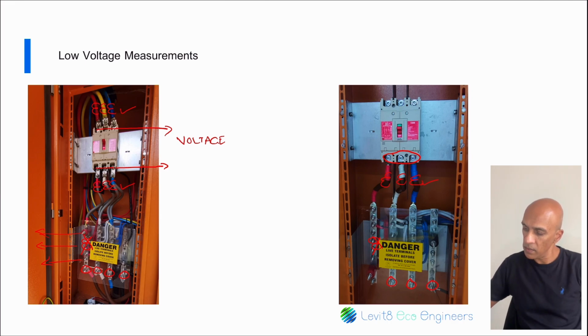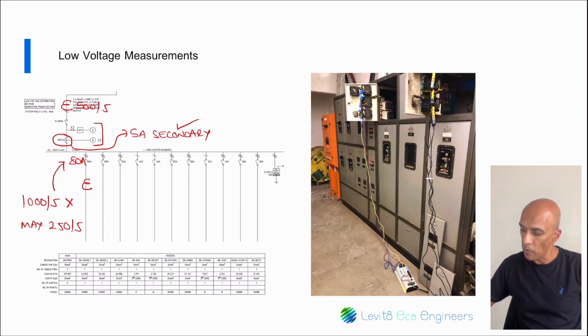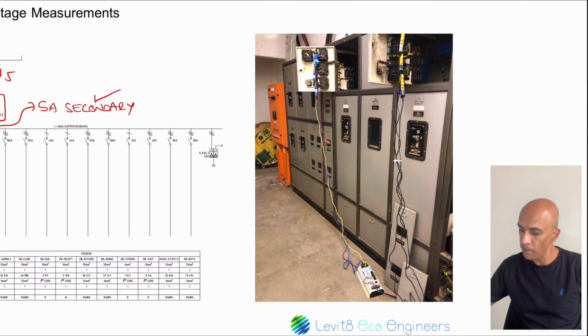this as a typical electrical panel where you have your main circuit breaker down here and you have bus bars. So these are quite the older type of panels. You have bus bars and then you have panel ammeters and voltmeters. And this is where you could typically also measure your currents. It's better recommended to measure your voltages from the bus bars or from maybe a feeder circuit breaker. But to measure your current, it would be quite convenient to measure at the back of these meters.